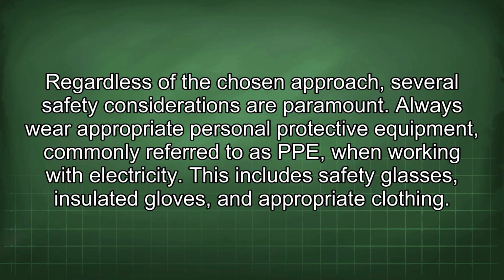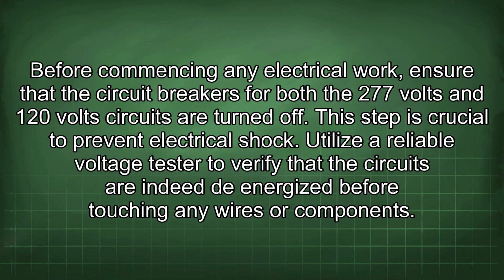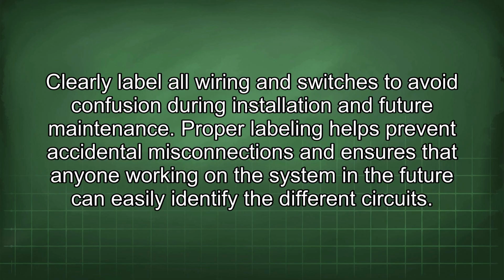Always wear appropriate personal protective equipment, commonly referred to as PPE, when working with electricity. This includes safety glasses, insulated gloves, and appropriate clothing. Before commencing any electrical work, ensure that the circuit breakers for both the 277 volt and 120 volt circuits are turned off. This step is crucial to prevent electrical shock. Utilize a reliable voltage tester to verify that the circuits are indeed de-energized before touching any wires or components. Clearly label all wiring and switches to avoid confusion during installation and future maintenance.